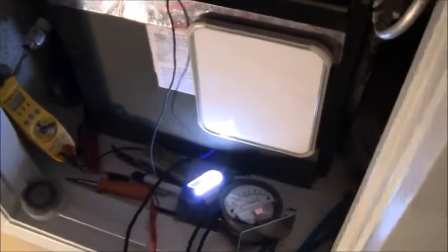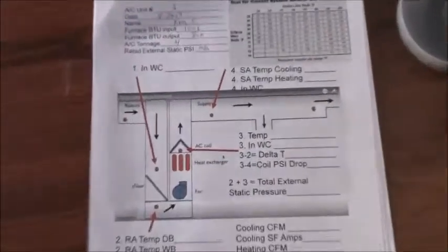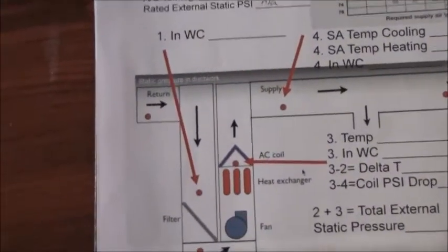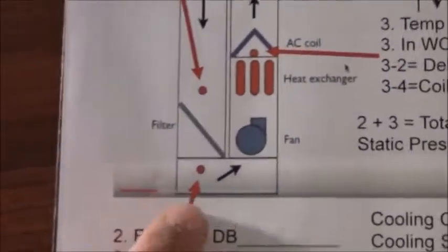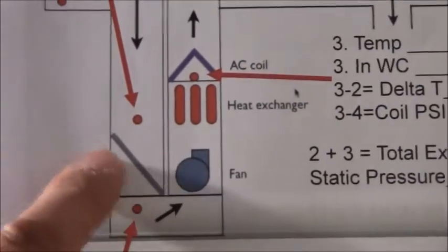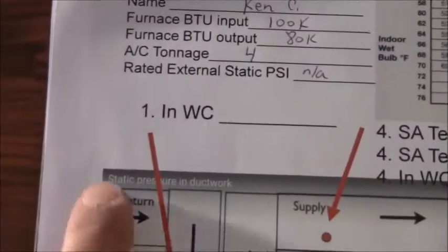Okay, and you can hear the fan is starting up. Now that the fan has started up, I want to get some readings and figure out what they are doing. Looking at my furnace chart, the first reading that I want to get is reading number 1, which is before the filter. I want to know what that is in inches of water column.